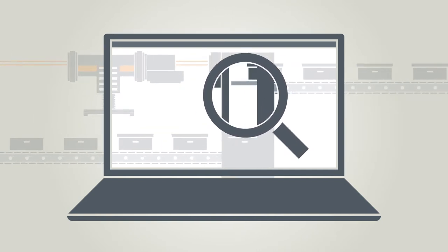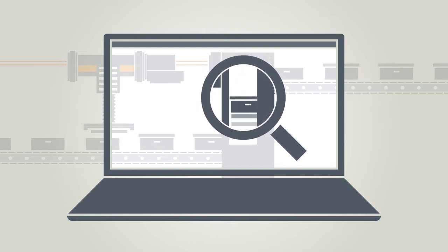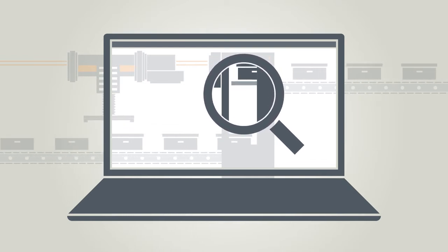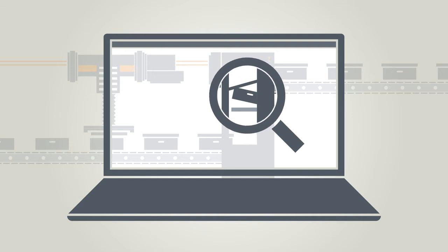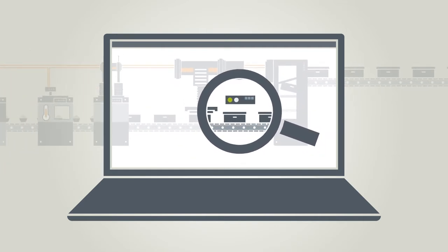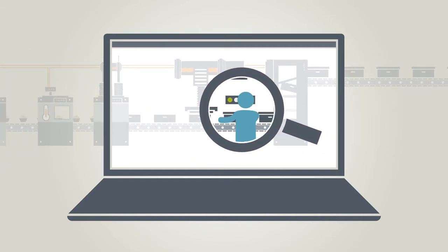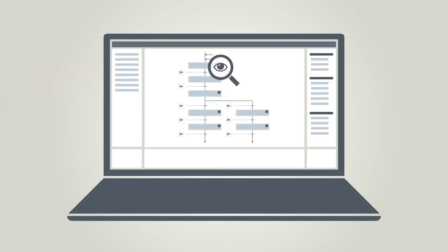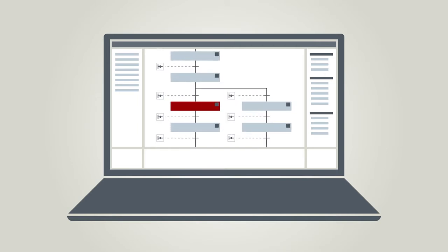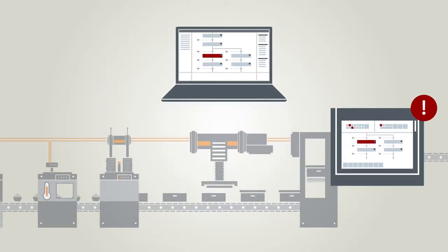Action and reaction supervision monitors whether a movement has started or stopped as desired. Position supervision monitors the status in an idle state, thus whether an object has changed its position unplanned. In the programming language Graph for sequential control systems, these monitoring functions are already integrated in each individual step. Alarms are generated here automatically.